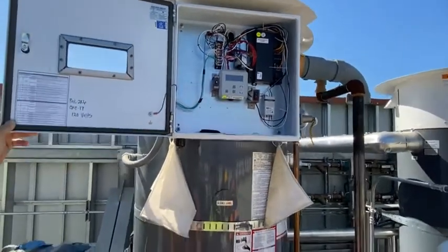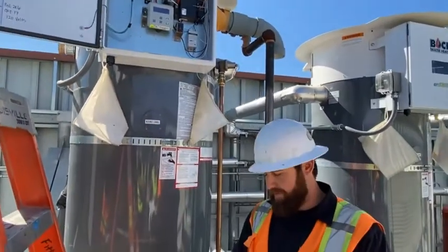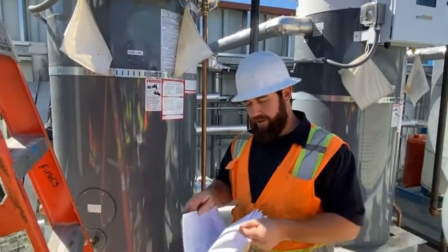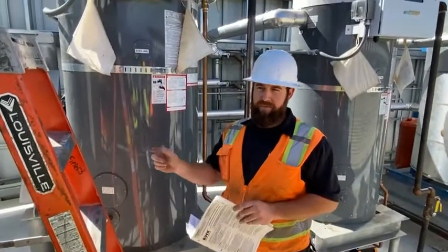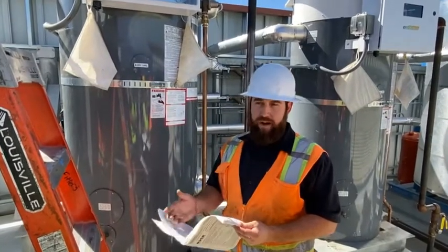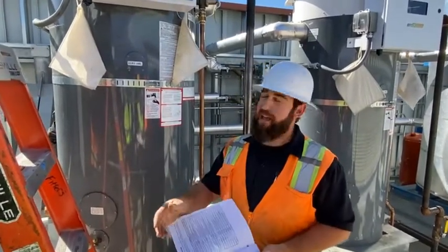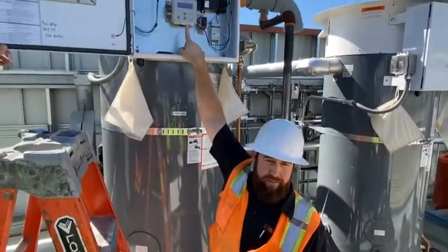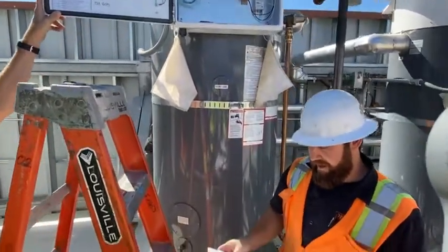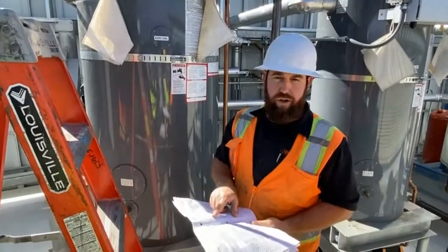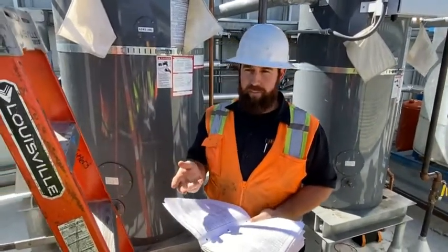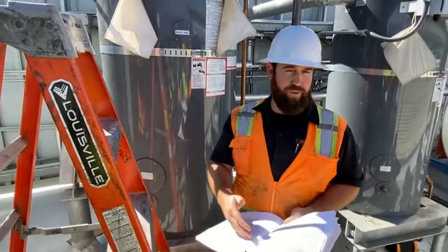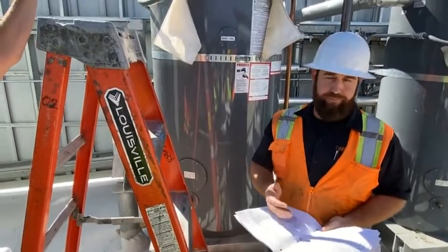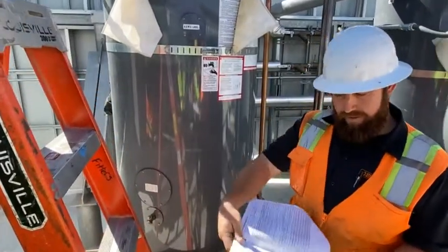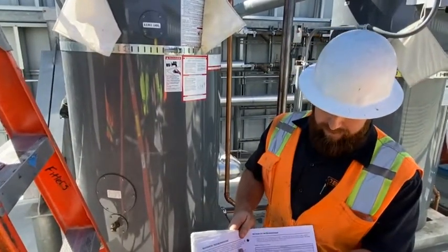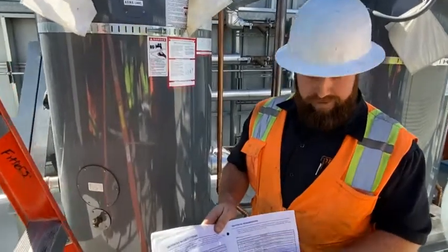If you do have any issues, the code will come up on the display. There's two different kinds of faults. There's an A followed by a set of numbers. That's the lockout error codes, which have to be reset. To reset, you push the I button, and that'll reset the unit. And then there's a set of codes, the blocking error codes, which are E followed by a set of numbers, and those will automatically reset once the issue is fixed. And then there's a whole troubleshooting guide in here. So we got the A's here, E's on this side.